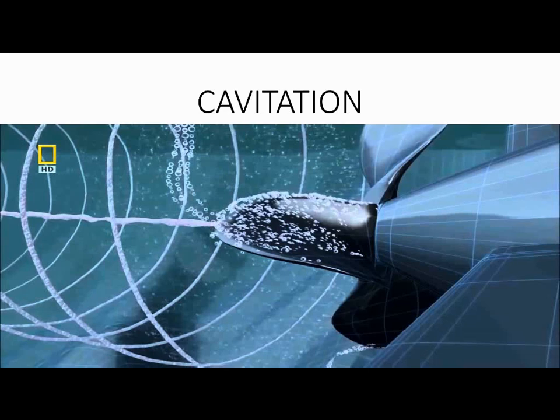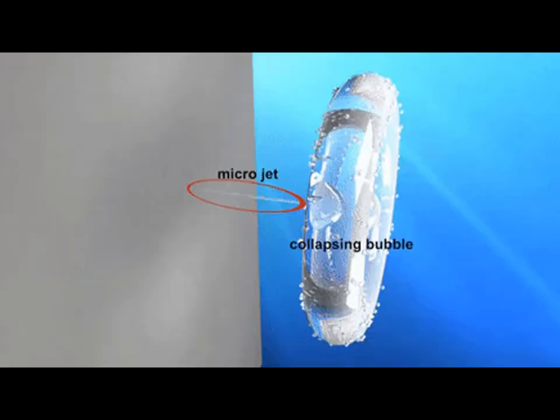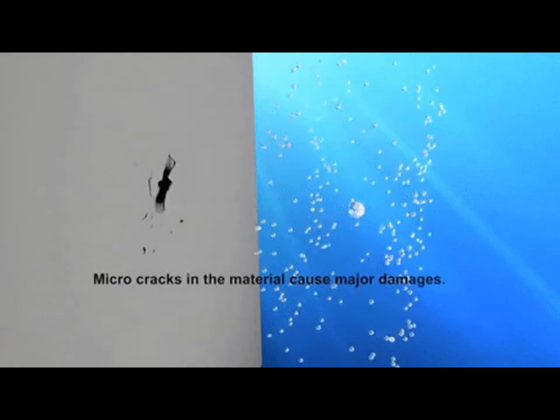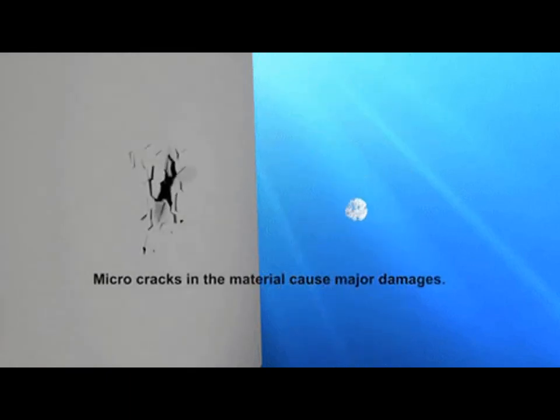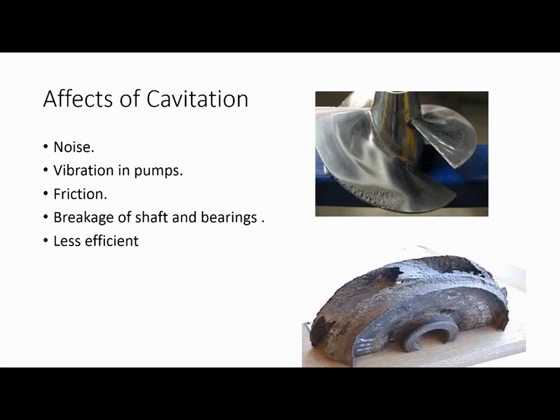Cavitation. Today we will learn about cavitation in pumps. Cavitation is the formation and subsequent collapse or implosion of vapor bubbles in the pump. It occurs because the absolute pressure on a liquid falls below the liquid's vapor pressure.